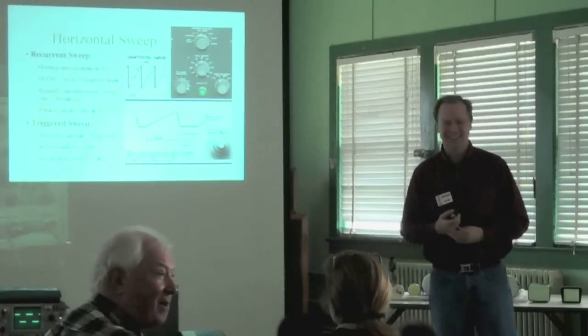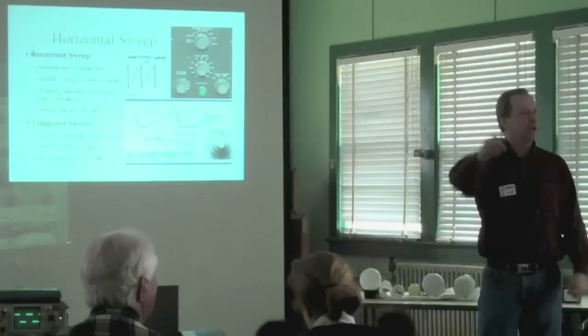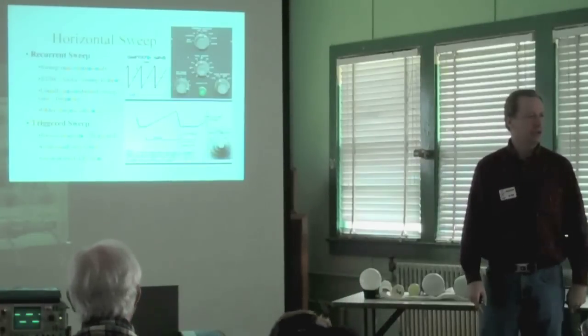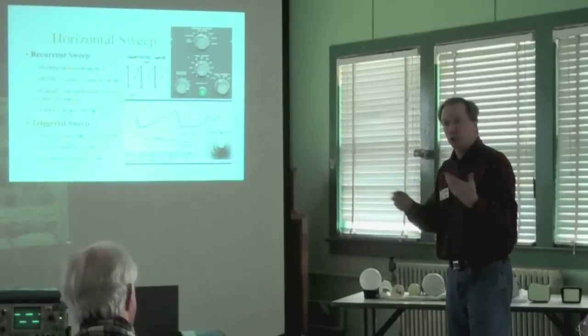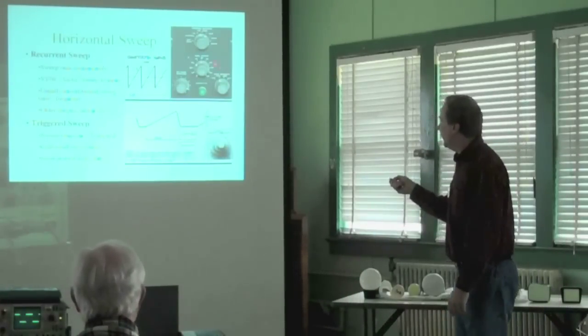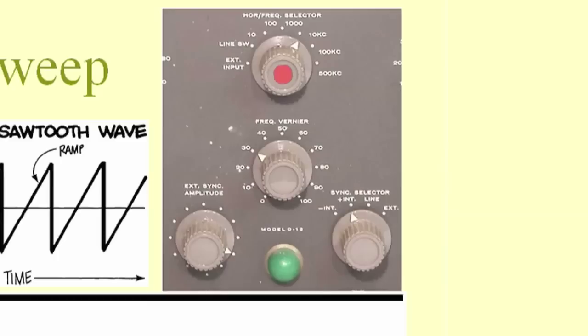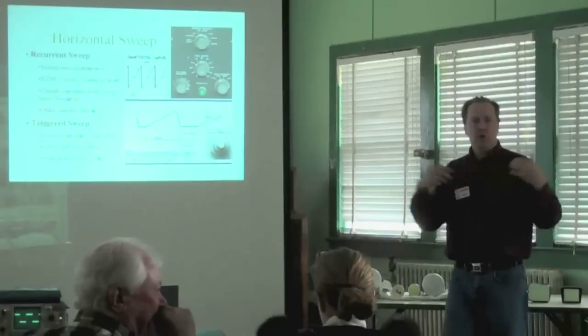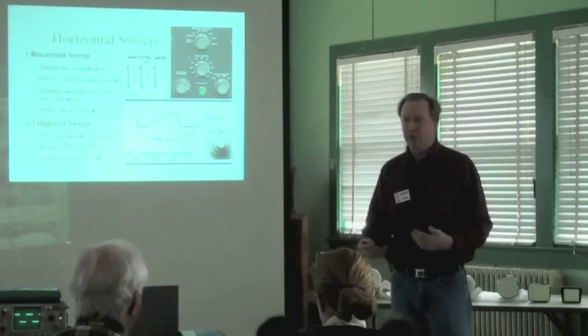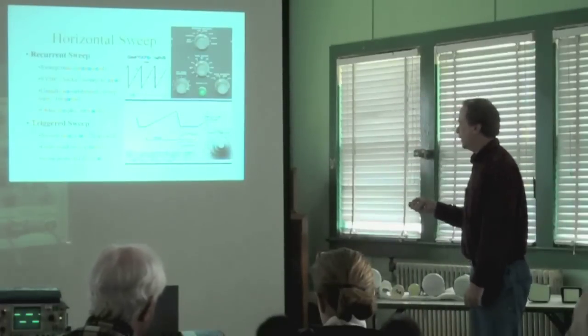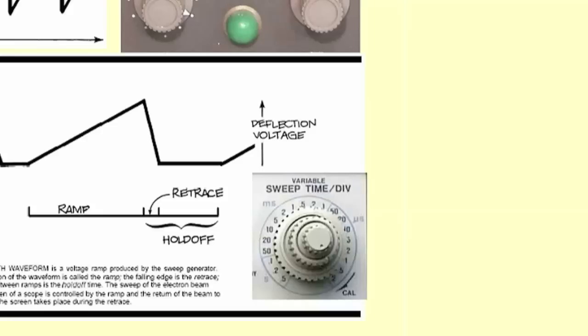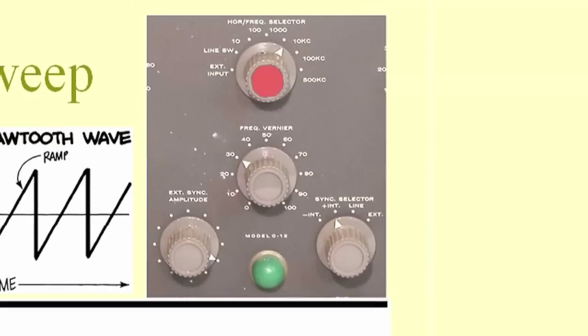Well, I said there's a recurrent sweep scope over here. I think one of the others over here was a recurrent sweep scope. So it's good to see it so you can recognize it. Another dead giveaway is that the horizontal is generally not calibrated. Yep. So if you're out looking for one, keep an eye out for something that's got some trigger controls. They'll typically have a calibrated microseconds, milliseconds, time per division type of horizontal control, as opposed to a vernier and a range switch. Okay.